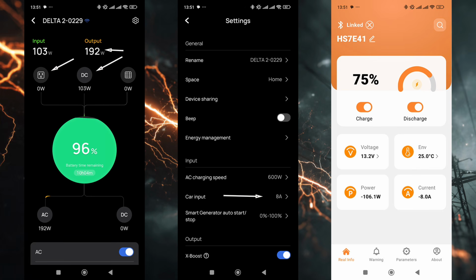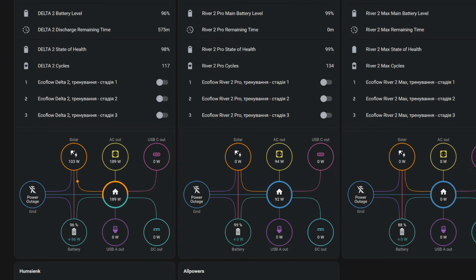In the first screenshot, you can see it is currently delivering 192 watts, the moment the refrigerator is running and receiving a little over 100 watts. The second screenshot shows the current port settings, where I set the maximum to 8 amps. The third shows the battery BMS, which indicates it is currently discharging at 8 amps. That is why I conducted the test at a load of 120 watts, slightly more than needed in practice. This is what the animation of this process looks like in the interface.